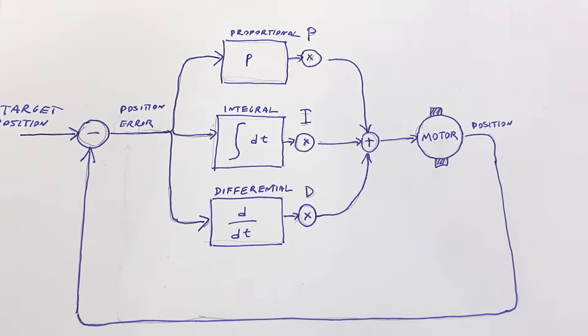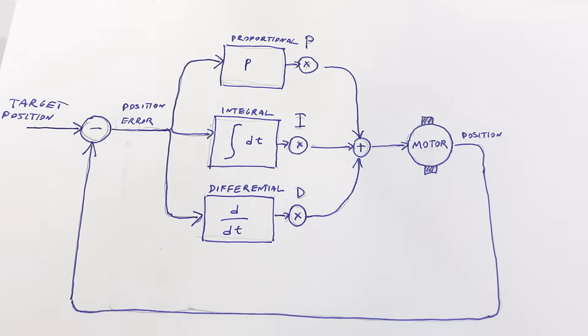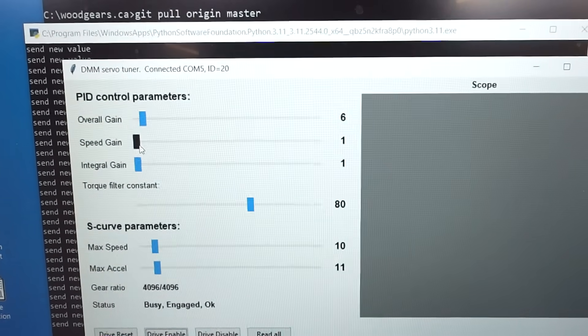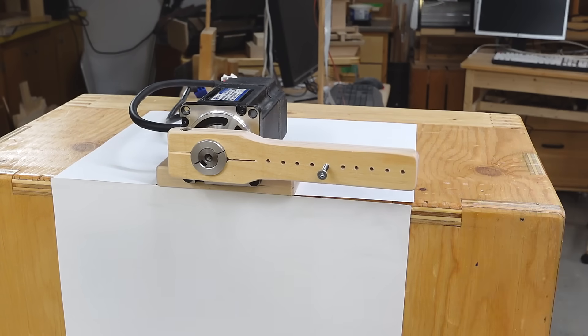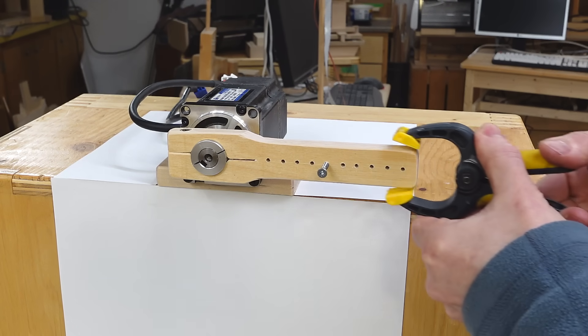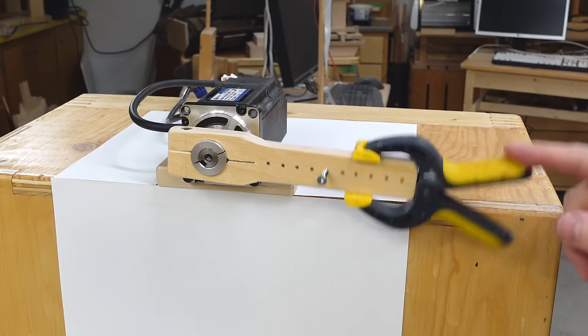If we're approaching an intersection in a car, we don't want to overshoot, so depending on how fast we're going we apply the brakes before we reach the stop line. This is where the differential term comes in — it basically adds speed to our position so it anticipates where we're going to be and stops earlier. On the DMM servo this is called speed gain. Setting it to maximum, if I force the motor off position and let it shoot back, it doesn't overshoot, though it seems slightly sluggish. Even with more inertia it doesn't overshoot like crazy.